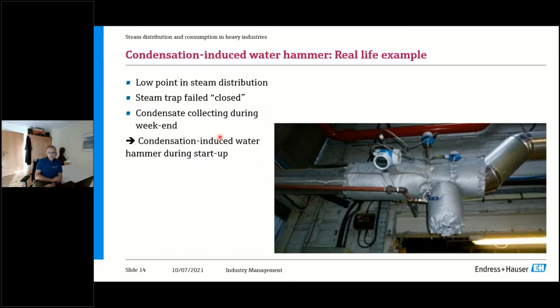A problem that typically occurs in steam lines is water hammer. And in this case, this customer experienced condensation-induced water hammer. What was the problem? You see we're here at the low point, and well, that's good practice. They have a T-piece with a steam trap sitting here. But the problem was that steam trap was not working. So the entire section here was drowned, and steam was coming in after the weekends, and then you had condensation-induced water hammer. That means you had a collapse of that steam bubble that came in, and that resulted in huge impacts that even killed the old version of our sensor.